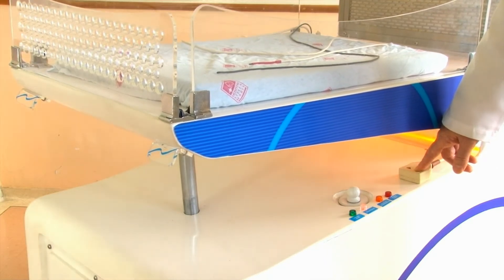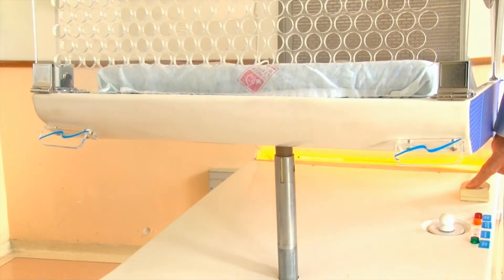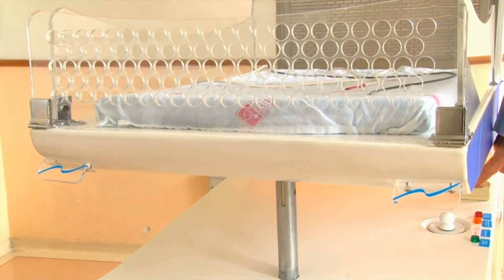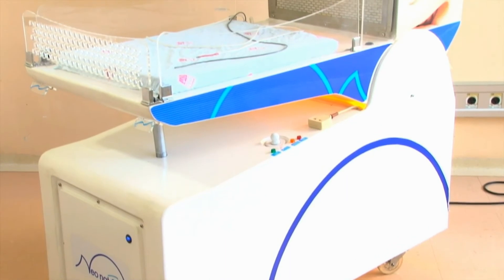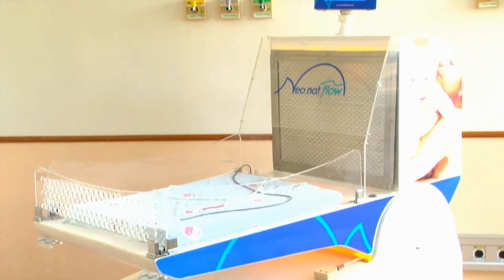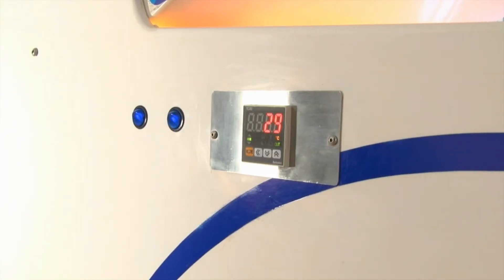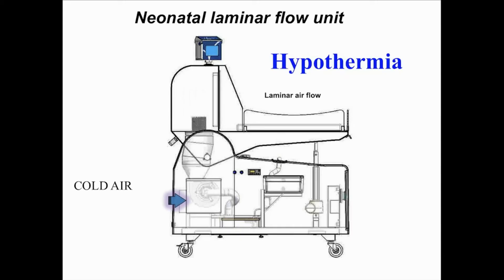This equipment may be used to care for newborns in the neonatal intensive care unit, and in place of the radiant warmer in the delivery room, with some advantages such as high isolation and humidifying the air. We have preliminary data and ongoing studies that this unit may decrease the infection rate in the newborn intensive care unit, and can also be used to deliver servo-control total body hypothermia for the treatment of newborns with hypoxic ischemic encephalopathy.